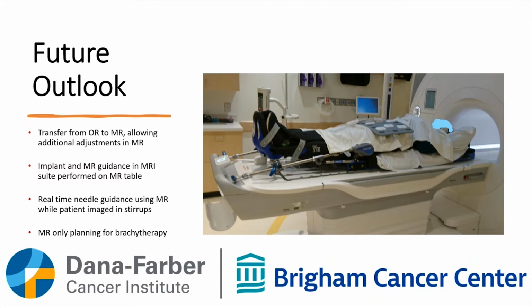Also, something that we've tested in the past, as mentioned by Dr. Dyer earlier: we have a suite in the hospital that's an OR, an MRI, and a CT all in the same area, where a patient can be transferred from one area to the next for imaging and planning. The issue that we ran into there is that we would do the implant in the OR with a Dyer system, but that Dyer system wasn't MR conditional. Let me go back a step. The stirrups were not MR conditional. The actual sled itself was. But when we went to transfer the patient into the MRI, we weren't able to keep the same stirrups on. So if there needed to be adjustments done via the MRI, due to MRI images before the implant was complete, we weren't able to do that with the same system that we used in the OR. With this system, that allows that.